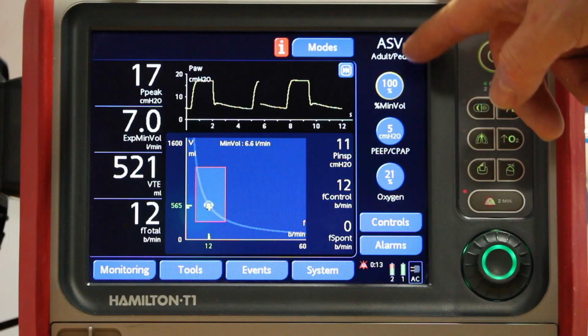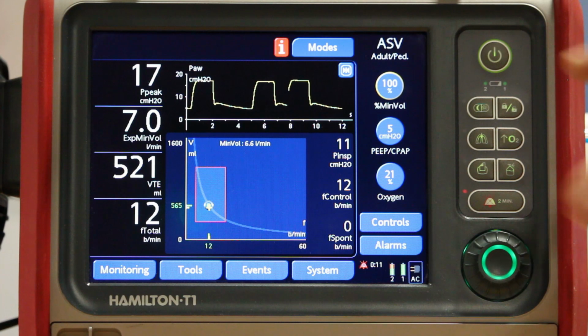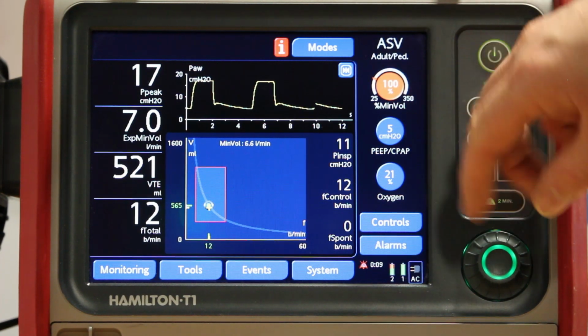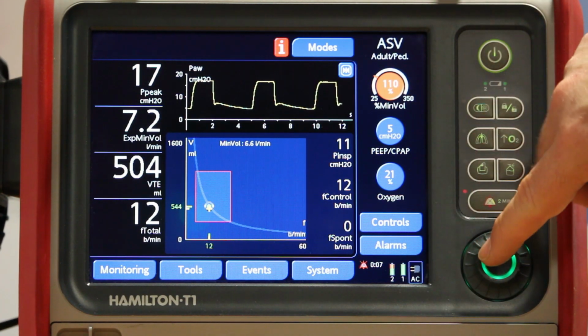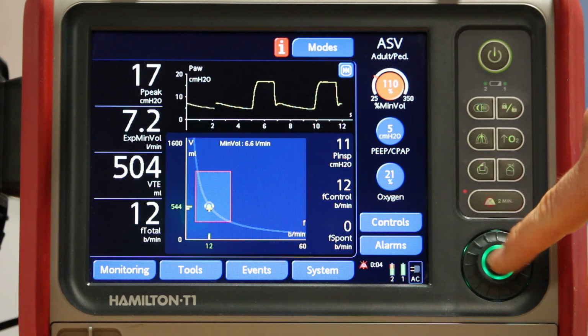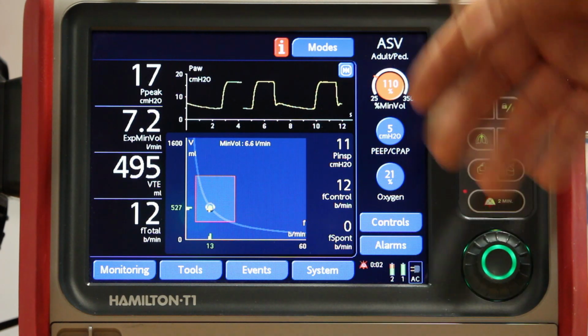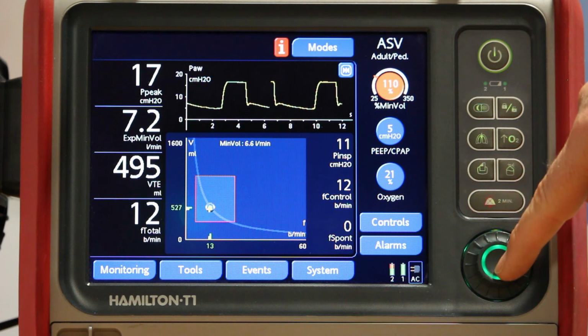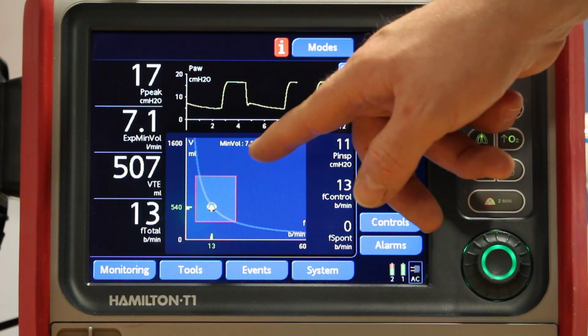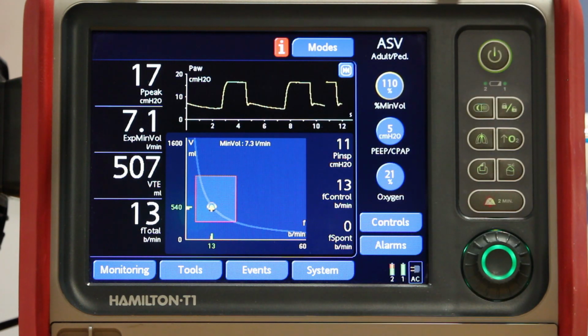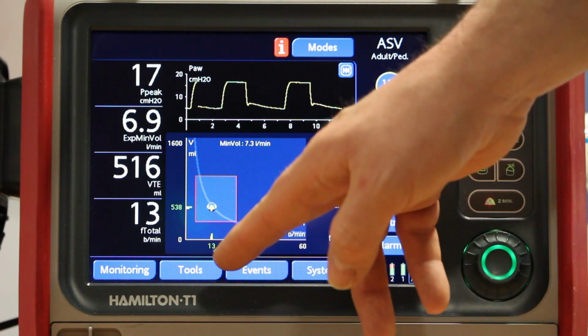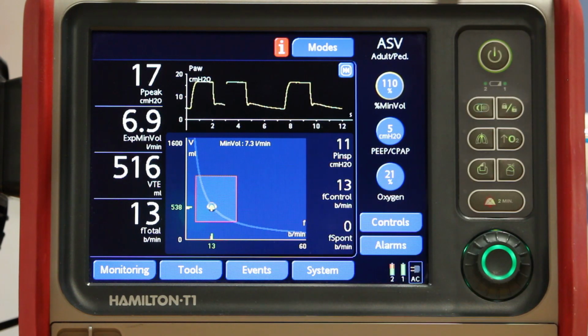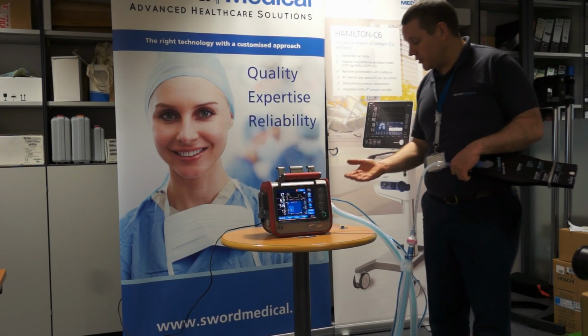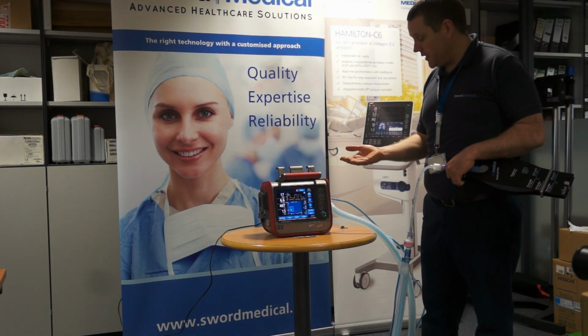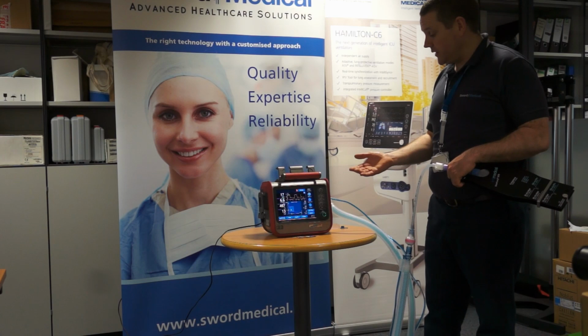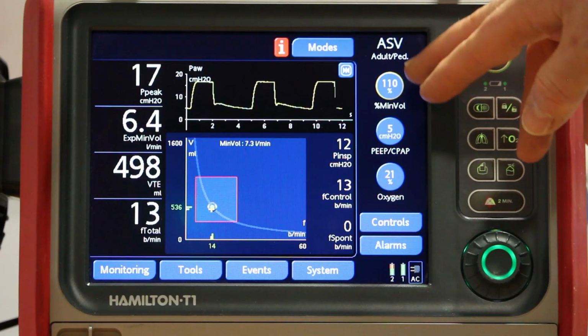So here with ASV, we're controlling the minute volume. So rather than turning the rate up to turn up the minute volume, we just turn up the minute volume itself. So Hamilton recommend 10% increases. So I see a rise in CO2, and I want to scrub it out. I'm going to go from 100% to 110%. My target went from 6.6 litres a minute to 7.3 litres a minute, and my frequency went from 12 to 13. So rather than using frequency or pressure or tidal volume to increase or decrease the minute volume, we just increase or decrease the minute volume itself. So that is ASV.